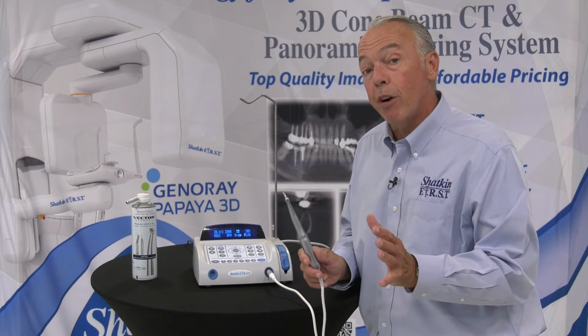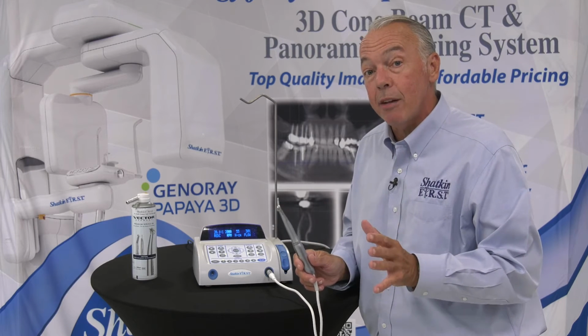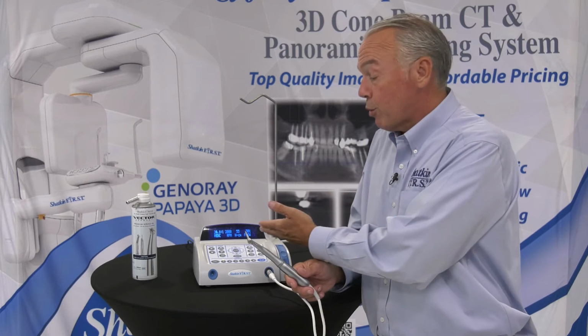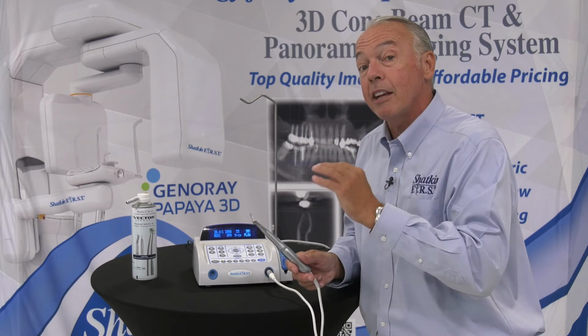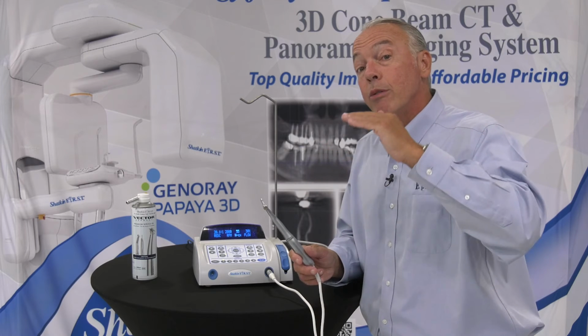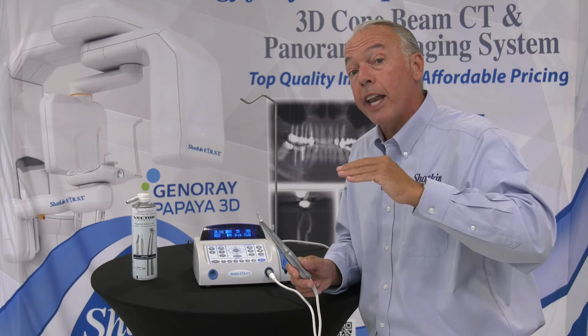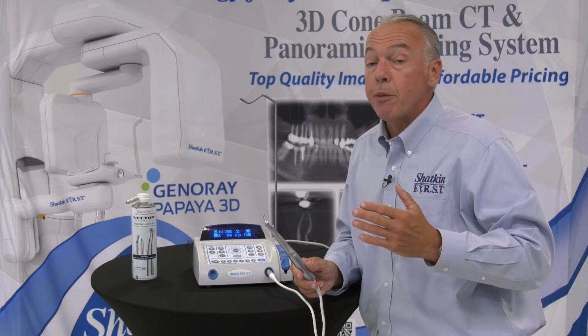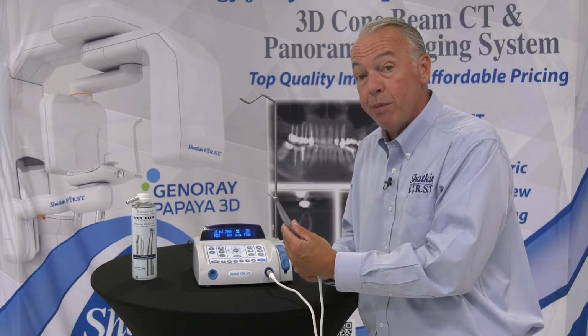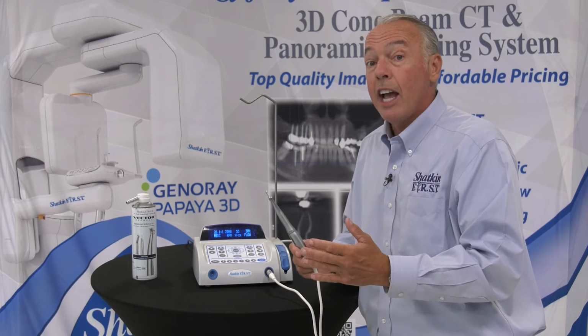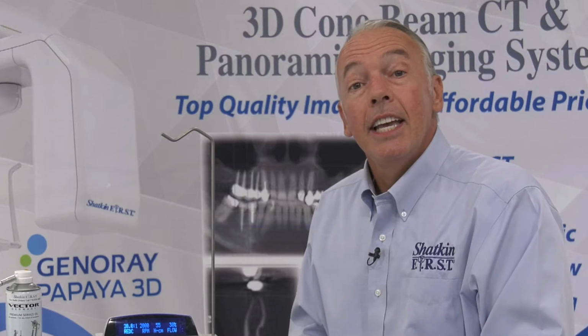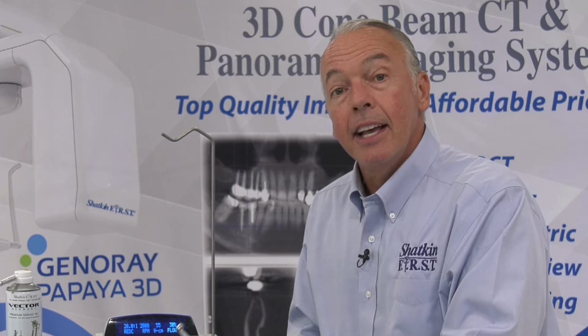And it's extremely important for the implant placement to know exactly where we sit with our efficiency. To know that if I just got 76%, which is anything from 75 and greater is perfect. If I go 76, then I go down to 61, then I go down to 40, then I go down to 30, it's a pretty good idea that I either need to have my handpiece maintained or looked at, or I should have a backup handpiece to go in. And another benefit for having an extra handpiece in your office is not having to wait for autoclave. So you can move right through your patients, keep your day on track. Having a second handpiece is so important.